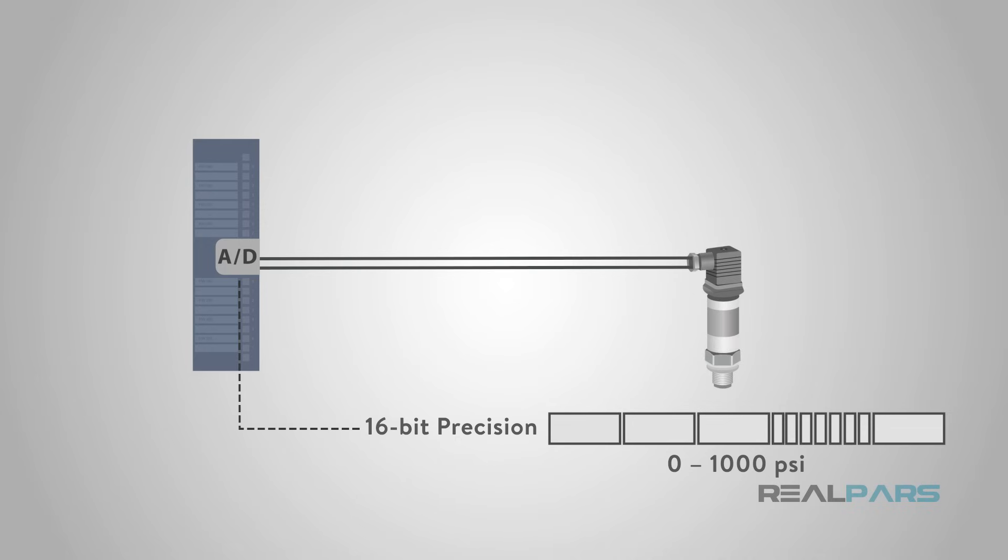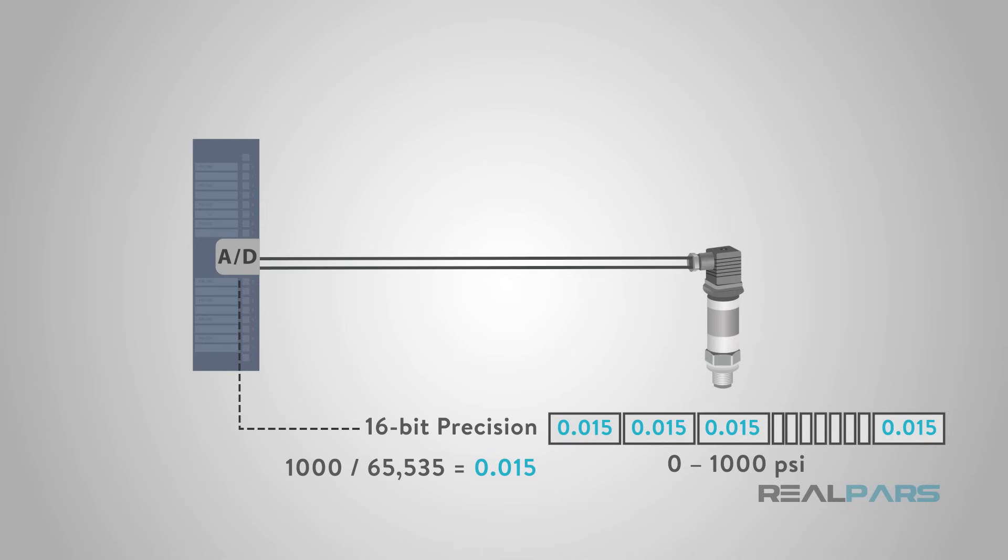This means that for a 0 to 1,000 PSI pressure sensor, the granularity of the signal value is 1000 divided by 65,535, or 0.015 PSI. This level of precision would be sufficient for most applications.